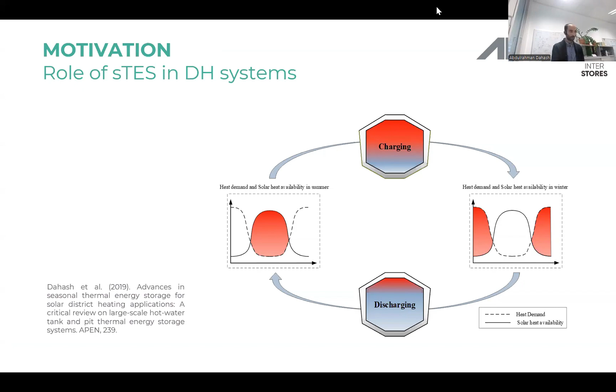During summer you have surplus heat that you would like to capture via solar thermal collectors, then inject it into a large-scale thermal energy storage via charging. Later during winter, when space heating demand is highest and solar heat availability is lowest, you start discharging. By that, you complete one cycle on an annual basis. This complete cycle we call a seasonal cycle, and that's why we have seasonal thermal energy storage.